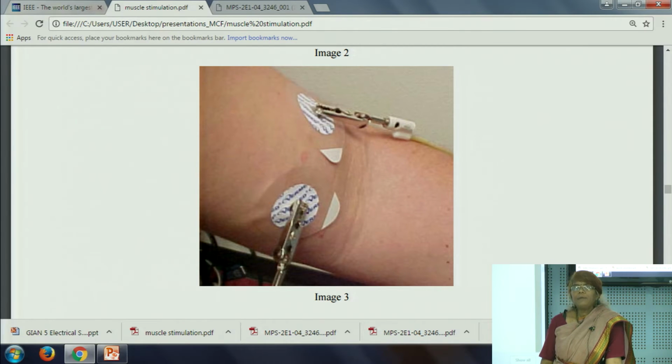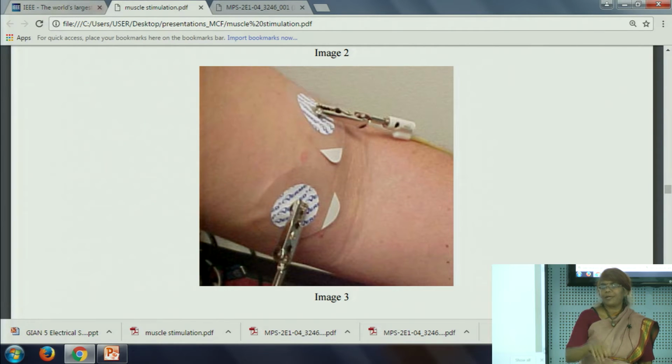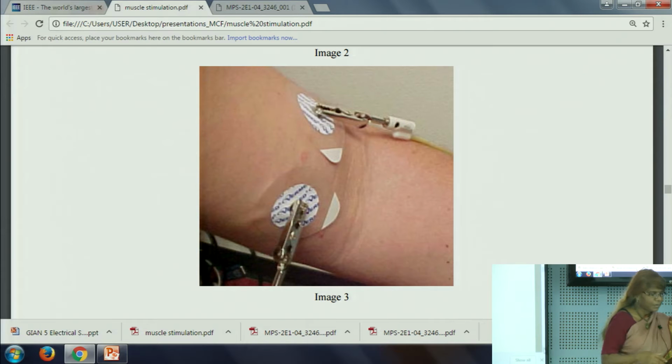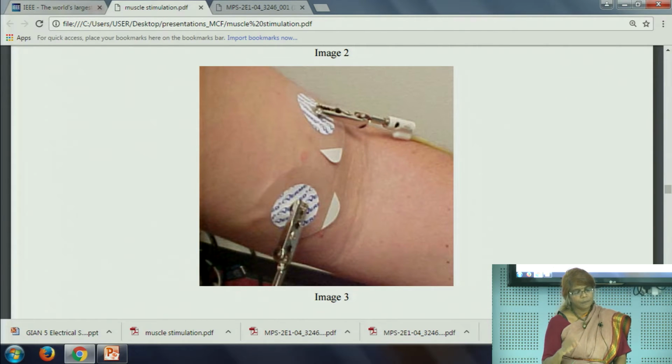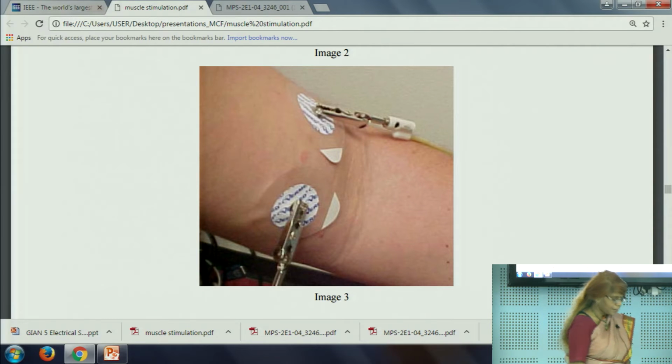Yeah, and so normally what do we do? We find the range. You apply very high voltage, make sure it burns, then you know you should be below that, and then you come down. Because you want to know the border. It's very difficult to go from small to higher. So you put the very high, it burns, then it comes down. Of course, we have to take what's that?